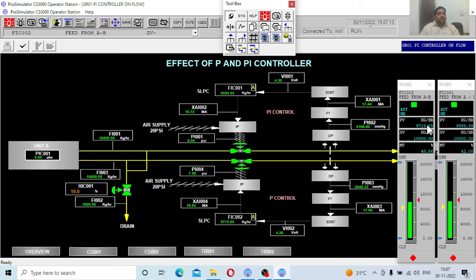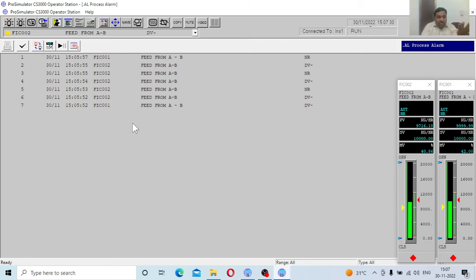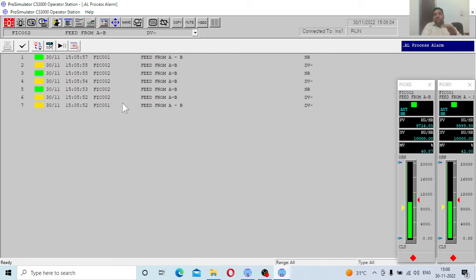This is the issue with P controllers — an error always exists between the set value and process value, and it takes infinite time to reduce this error. Now let us look at the alarms. Different color codes are given: green, yellow, and red. Right now there is no red. Yellow means a deviation has been detected. For FIC002 there is a negative deviation (DV minus) because the process value is less than the set value — that is a negative deviation alarm. For FIC001 there is also a minor deviation shown, and based on these alarms operators in an actual plant will judge what is happening.